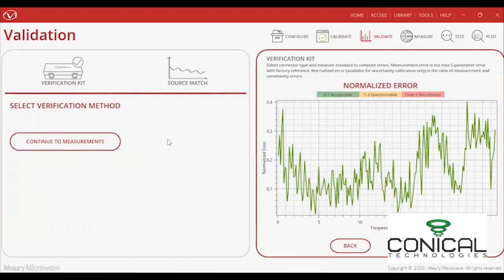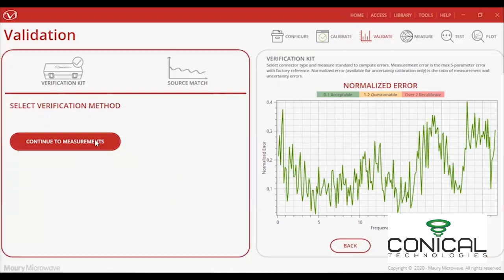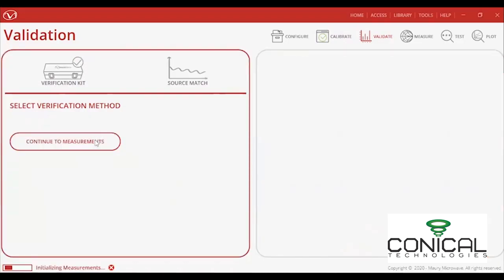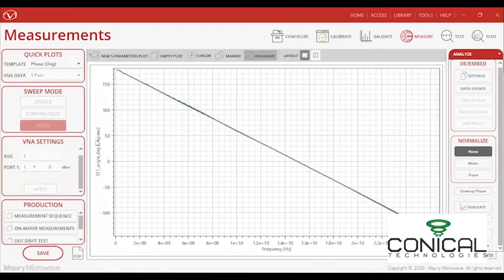This is where the benefit of having a characterized cal kit comes into play. The uncertainties included with the kit helps you decide if you need to calibrate again. This can now enable your 8510 to have a pass-fail criteria to enable the user to know how accurate their calibration is. Now that I'm done validating my calibration and have an idea of how accurate it is, I can move on to confidently taking measurements.